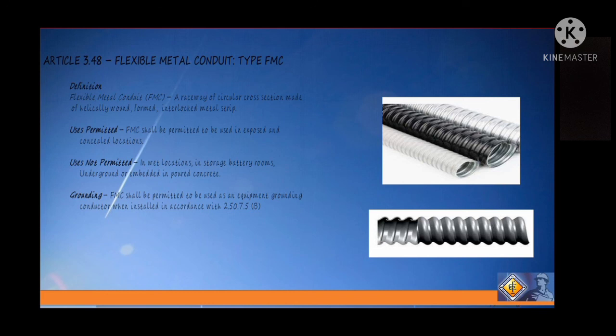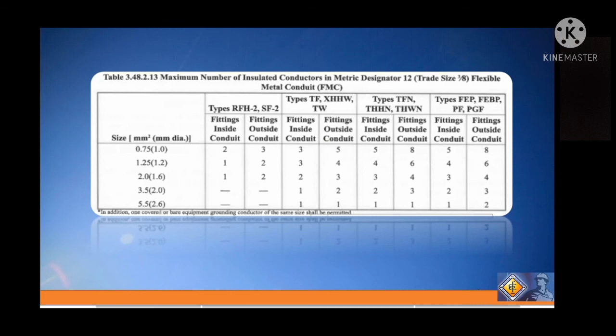In terms of grounding, FMC shall be permitted to be used as an equipment grounding conductor when installed in accordance with section 2.50.7.5b. So here's the table of the maximum number of insulated conductors in metric designator 12, which is the size of 3/8, flexible conduit or the type FMC. It shows the size and the types and the fittings inside and outside of the conduit.